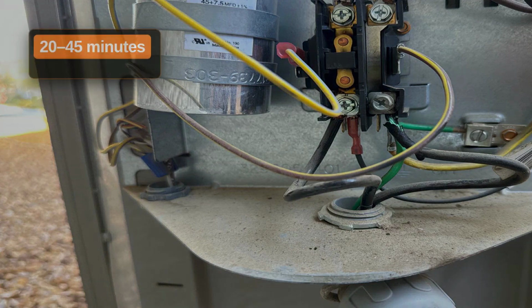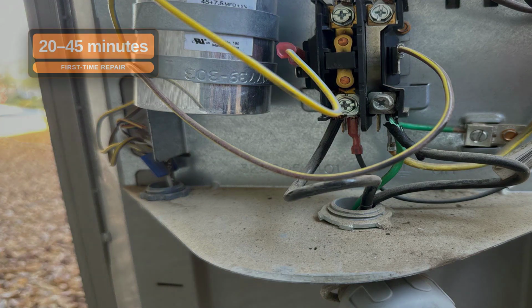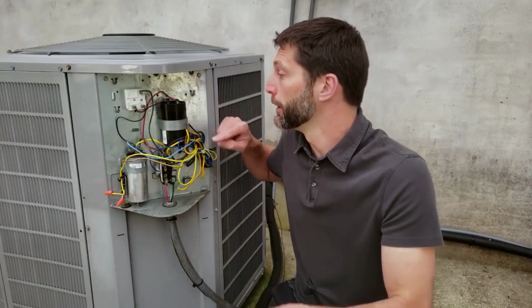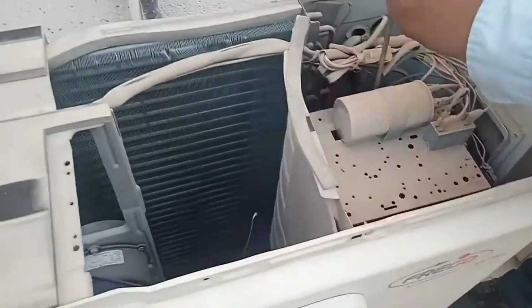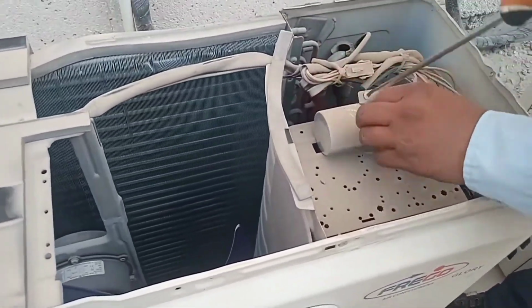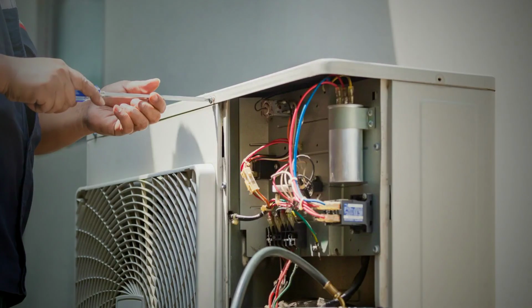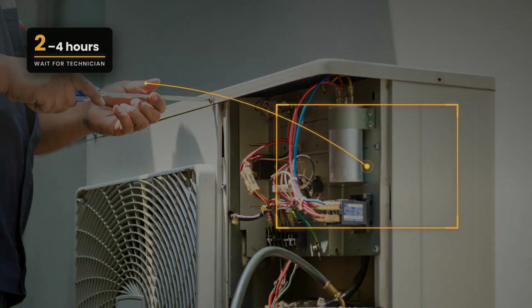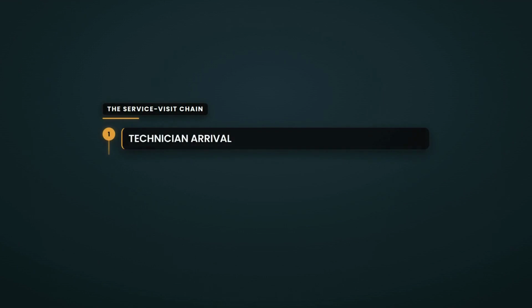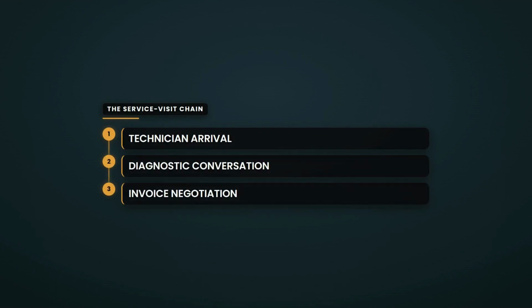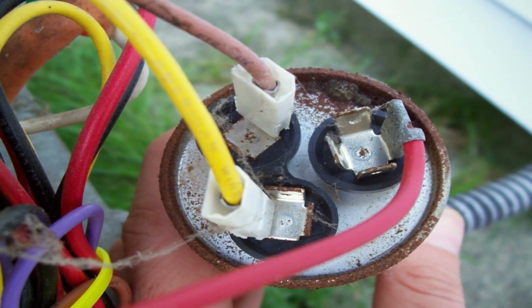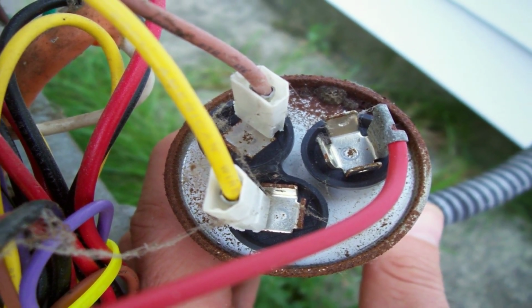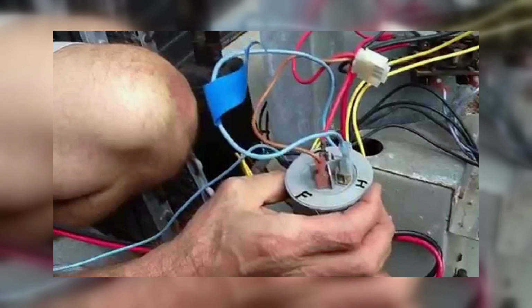Time investment runs 20 to 45 minutes for a first-time repair, including locating the unit, removing the access panel, discharging the capacitor, photographing and swapping the wiring, and testing the system. Compare that to a 2 to 4 hour window waiting for a technician to arrive, plus the diagnostic conversation, plus the invoice negotiation. The DIY path is not just cheaper, it is faster. The skill level required is genuinely low. The information barrier is the only real obstacle, and you are clearing it right now.